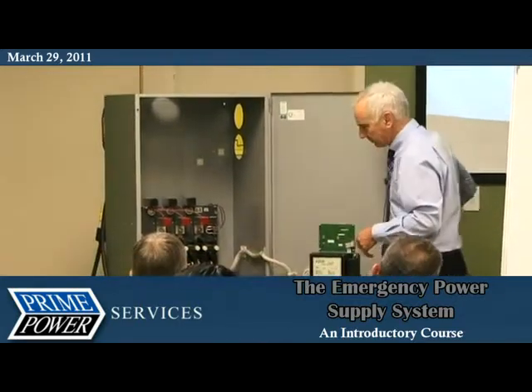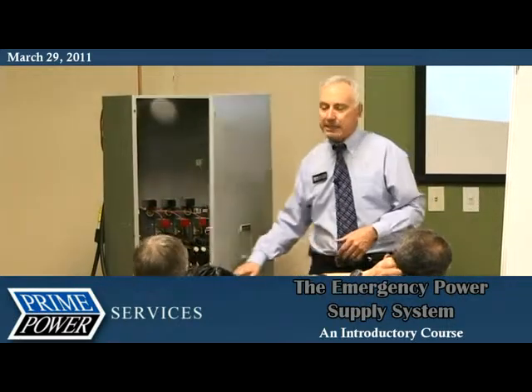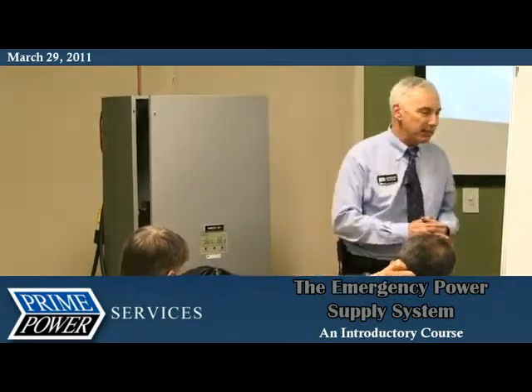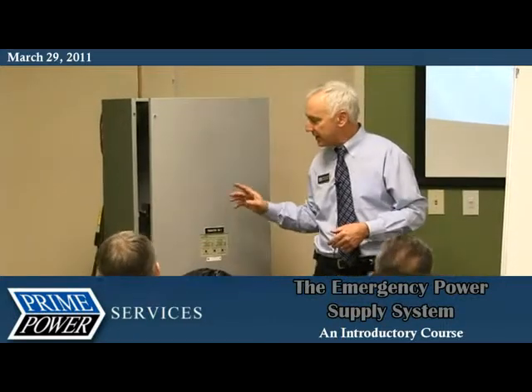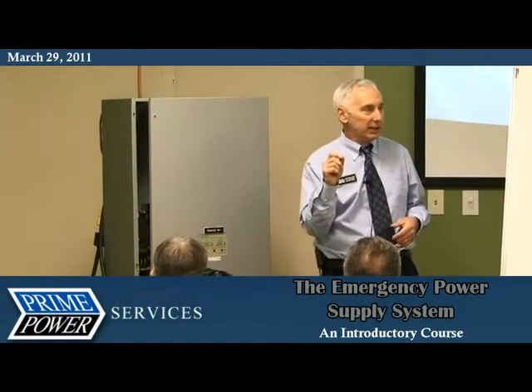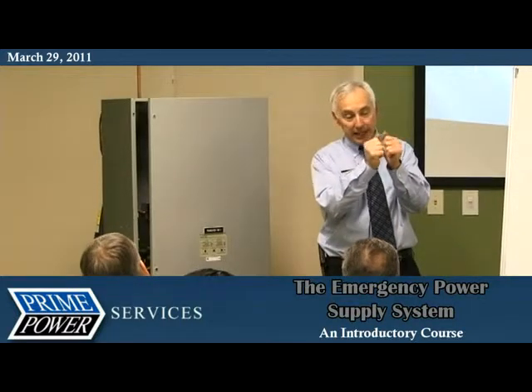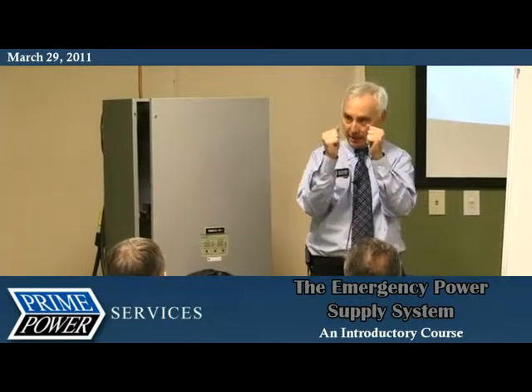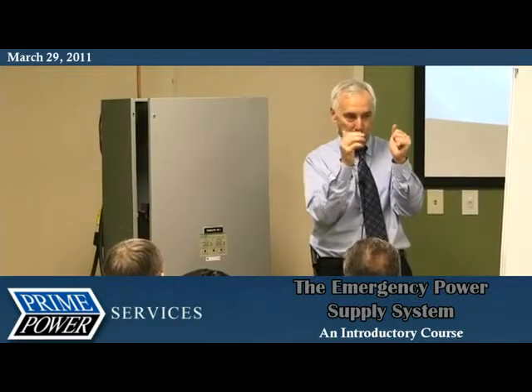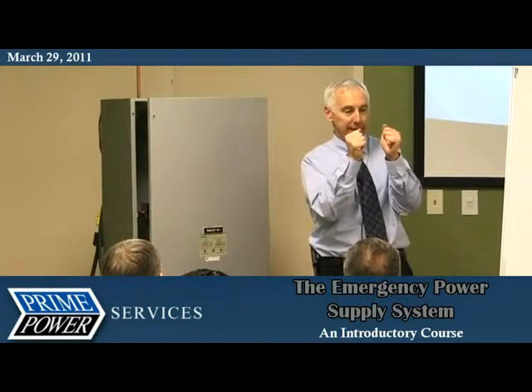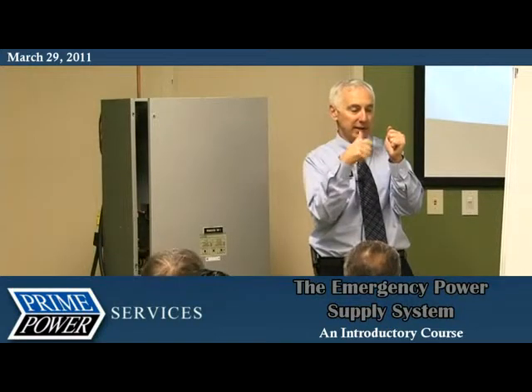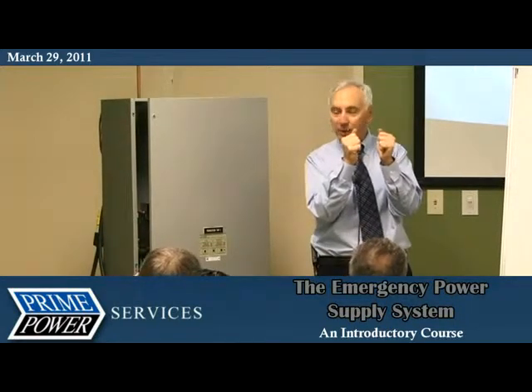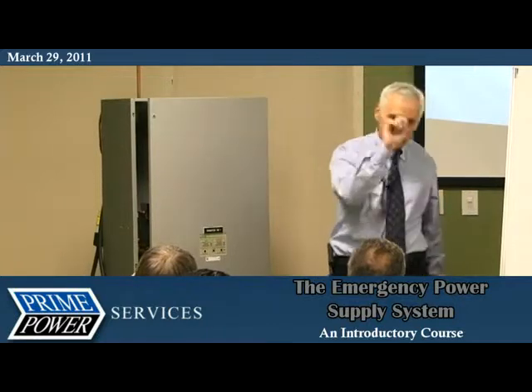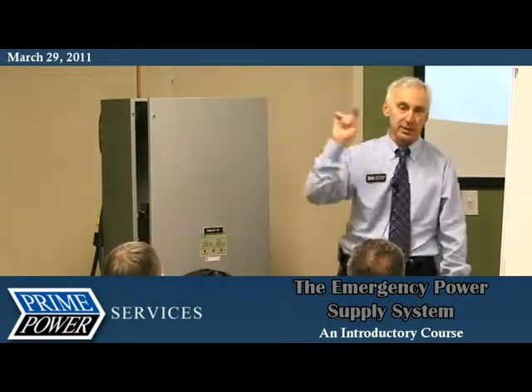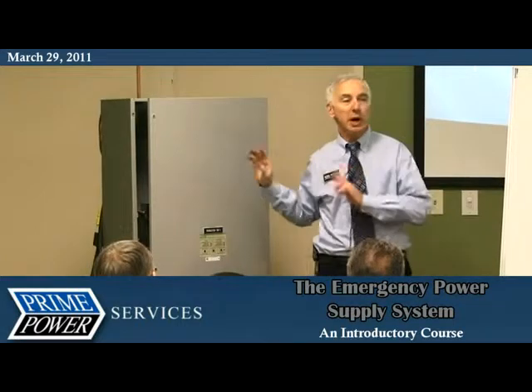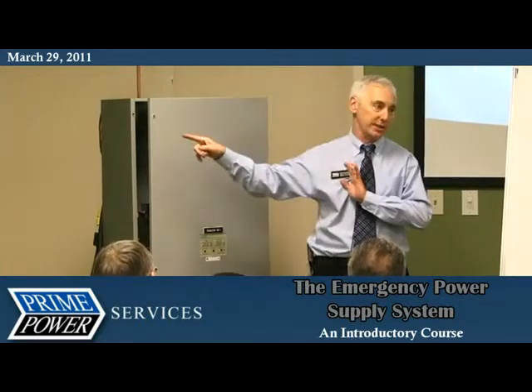The engine start circuit, to demystify this thing a little bit, is very simple. All it is: whenever normal power is there, it magnetically pulls apart a set of contacts in a relay, just opens them. So normal power is there, it's held open. As soon as normal power goes away, since there's no magnetic energy here anymore, the contacts close, it shorts out two little contacts, and we send a start signal. So it's fail-safe: anytime we don't have power on this switch, we're sending a start signal.